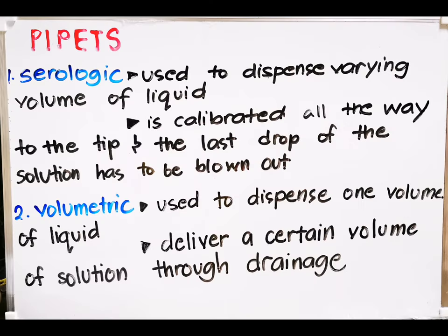Next, we move on to pipettes. We have serologic and volumetric. The serologic pipette is used to dispense varying volumes of liquid; it is calibrated all the way to the tip, and the last drop of the solution has to be blown out. The volumetric pipette is used to dispense one volume of liquid only, delivering a certain volume of solution through drainage, so we don't need to blow it out.